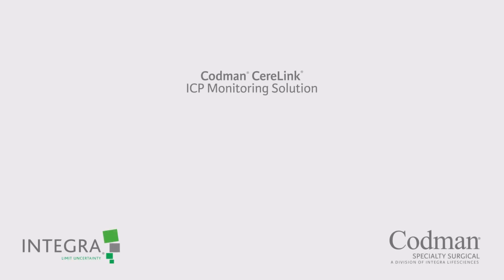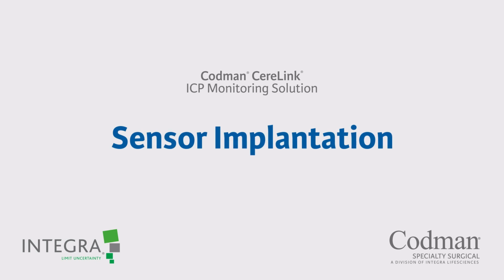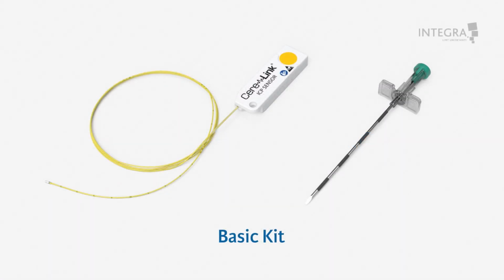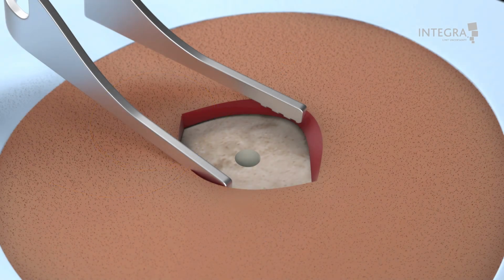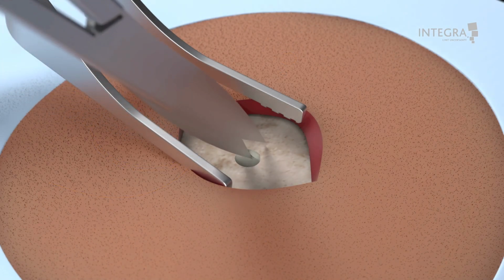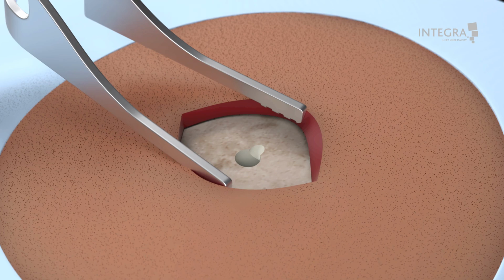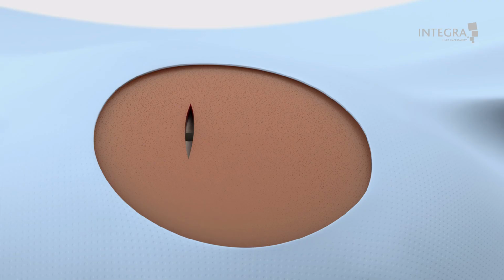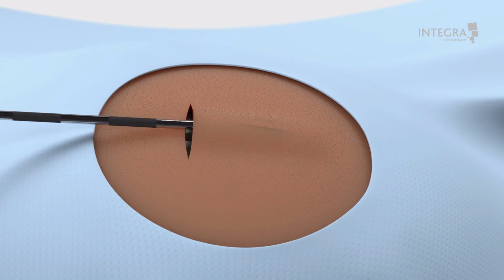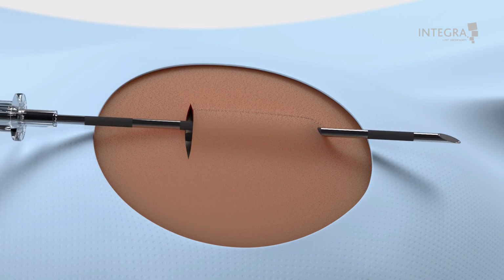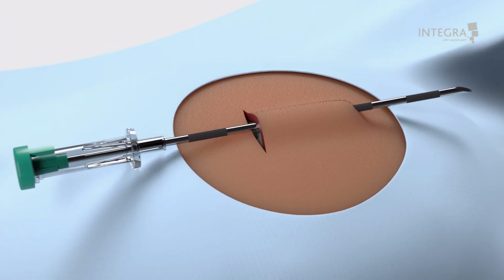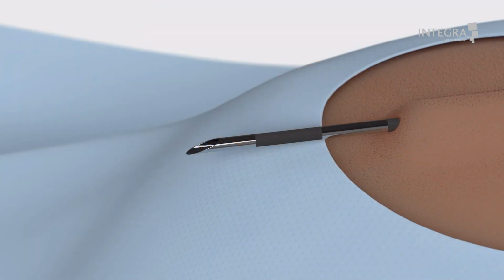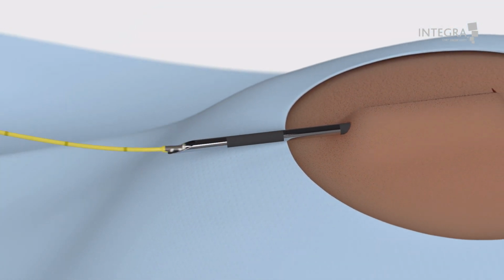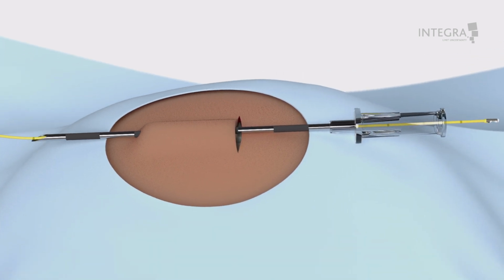3. Sensor implantation. The ICP sensor basic kit includes a CereLink ICP sensor and a 14-gauge Tuohy needle with a stylet. Bevel the burr hole edge on the side where the ICP sensor will exit. This will facilitate removal of the ICP sensor. Use the Tuohy needle to tunnel under the scalp from the burr hole site to the desired ICP sensor exit site. Remove the Tuohy needle stylet and thread the ICP sensor from the tip of the needle until the appropriate length for placement exits from the hub.